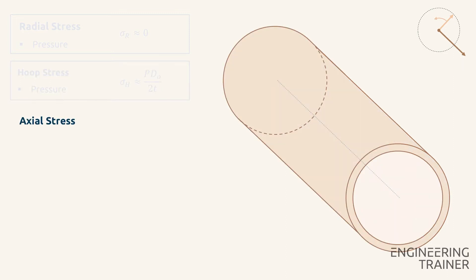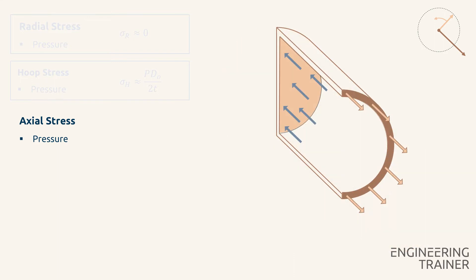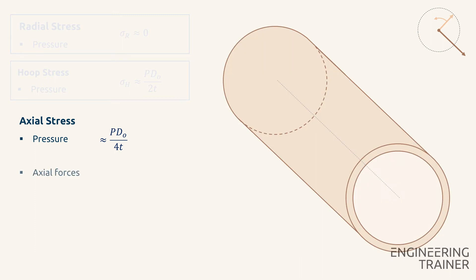This is different for the axial stress. We've seen that the pressure contributes to the axial stress according PD over 4T. But also other loads like external axial forces can cause an axial stress. An example could be the weight loads of connecting pipe segments. This contribution can generally be calculated as the external axial force divided by the cross-sectional area of the pipe.